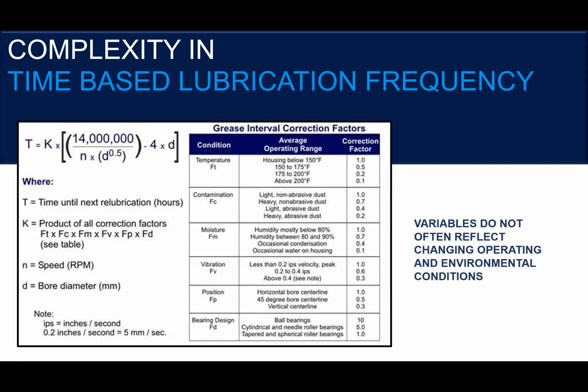Now people have started to address that by putting duty cycles into these calculations, but you're still making an assumption. Even look at these correction factors, say temperature. If your housing was, say, 151 degrees F, would you use a correction factor of 1 or 0.5? You're at the very low end of that 150 to 175 range. In fact you should probably be using something like 0.9, 0.98, or 0.7.